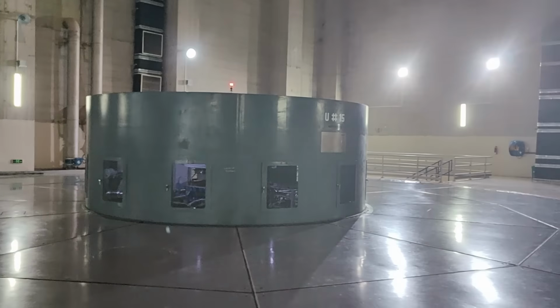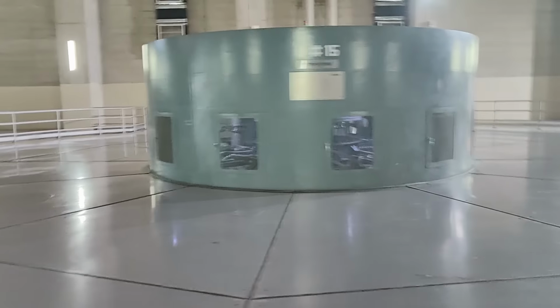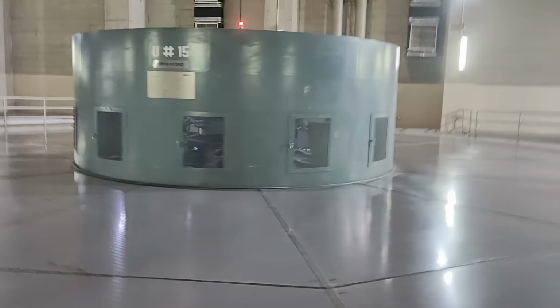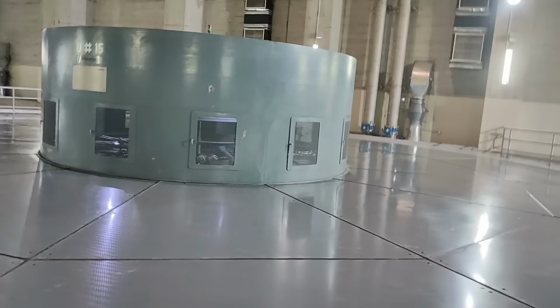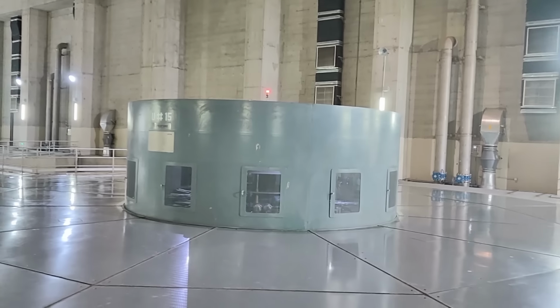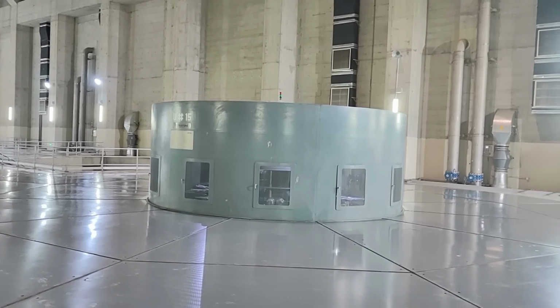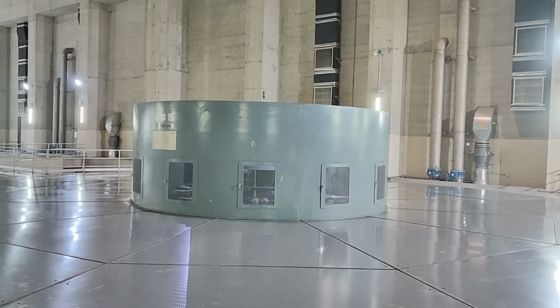And this is the moment where a simple spinning machine transforms into an energized generator. At this stage, the unit reaches SNL condition, which is called speed no load. The machine is now spinning at full operating speed and producing full voltage, but it is still disconnected from the electrical grid. So even though the generator is energized, it is not yet delivering real power.